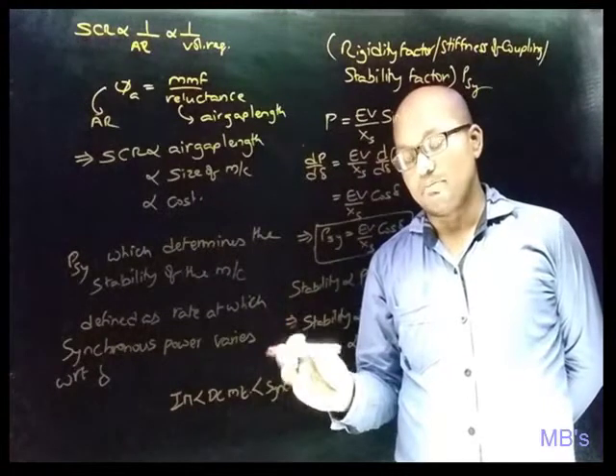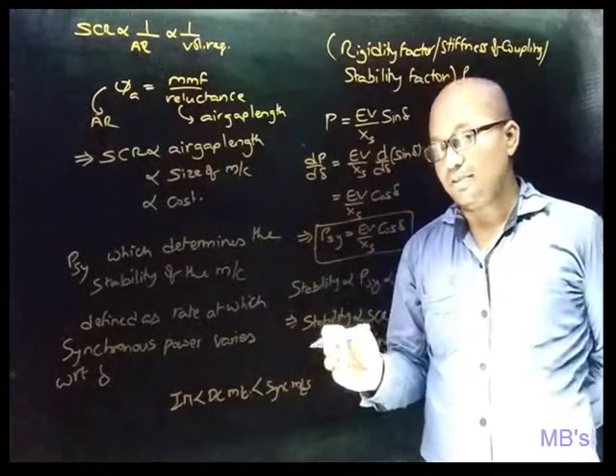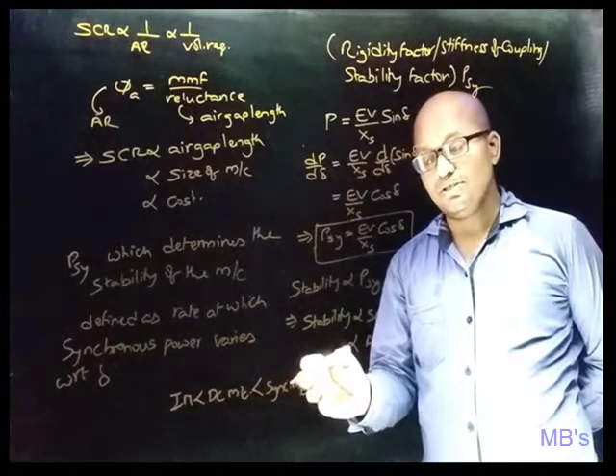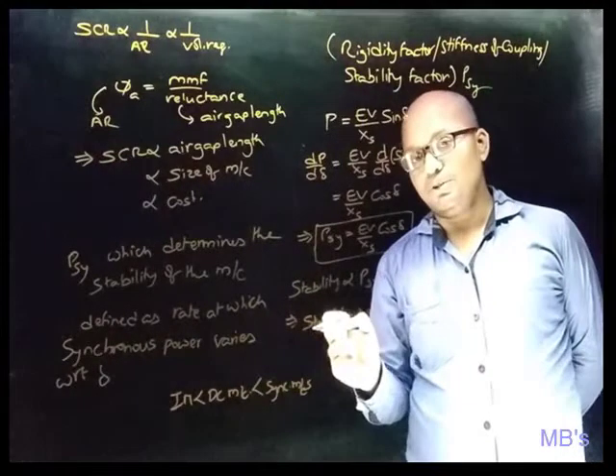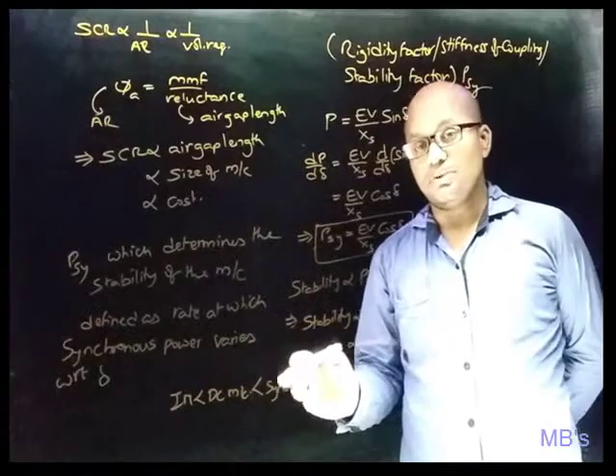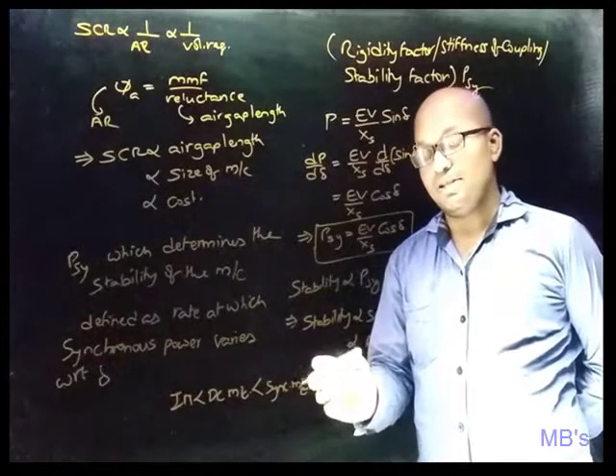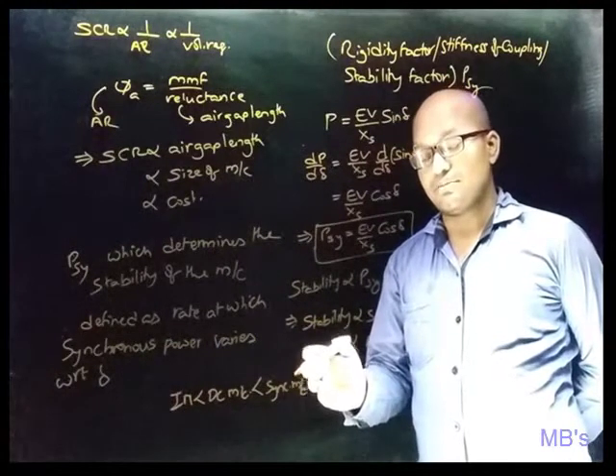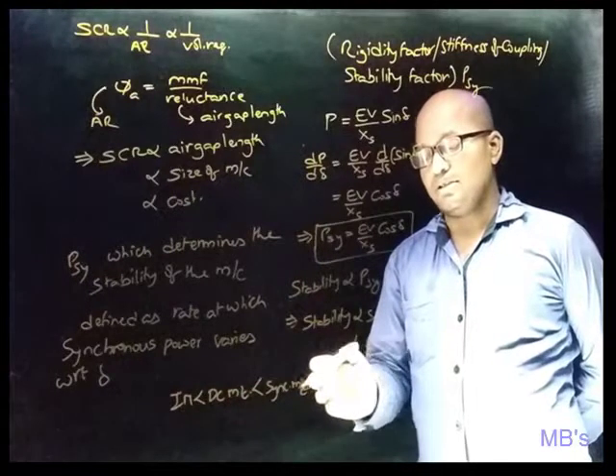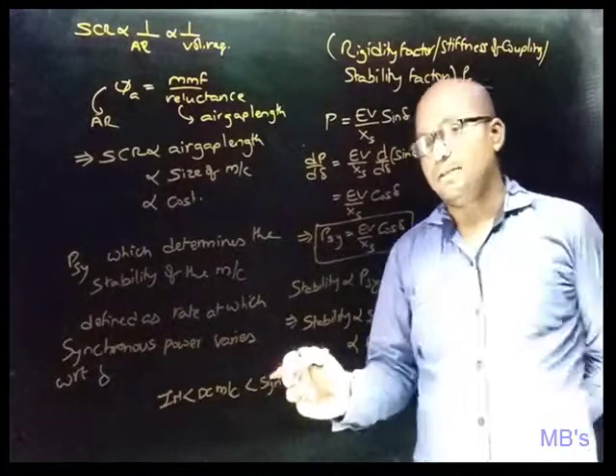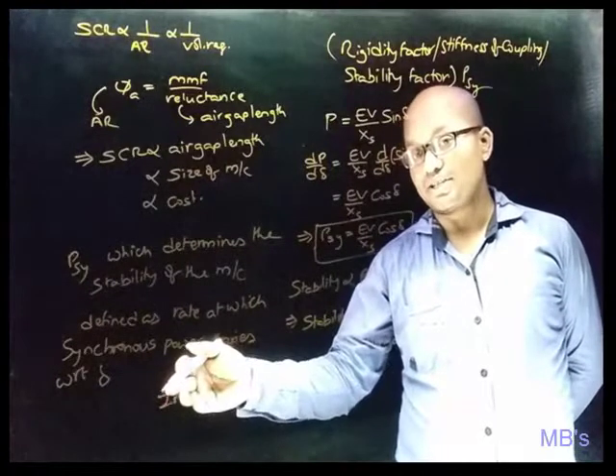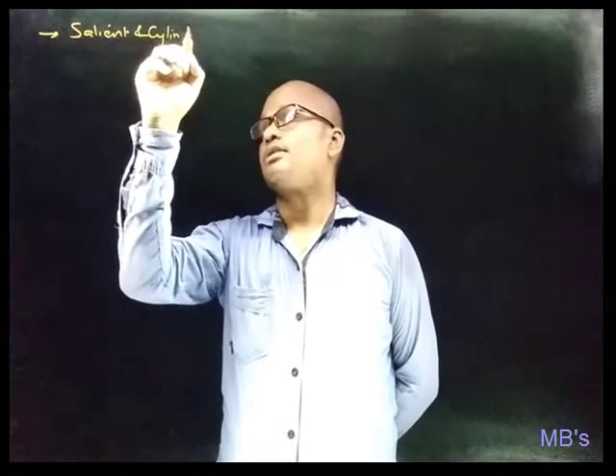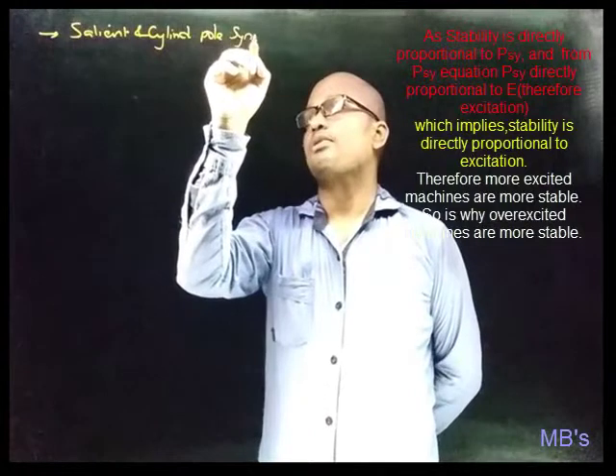Stability is directly proportional to the short circuit ratio and air gap length. Comparing air gap lengths: induction machines have less air gap, DC machines are in between, and synchronous machines have the most air gap length. The synchronous machine has more air gap than the induction motor because the induction motor is designed to operate at good power factors — a smaller air gap gives better power factor.